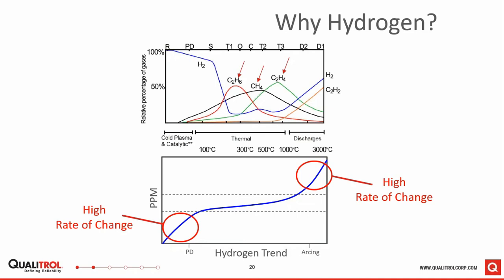The amount of free hydrogen in the oil that you're generating isn't going down. It's still increasing, just at a lower rate than in the PD range. And then once you get up to acetylene, you produce a significant amount of hydrogen again. So the takeaway from this slide is that if you're seeing a significant increase in hydrogen in a short period of time, typically it's because you have partial discharge or arcing happening in your transformer, and it's going to alert you that you need to take an oil sample to do a full analysis of what's going on in that transformer.